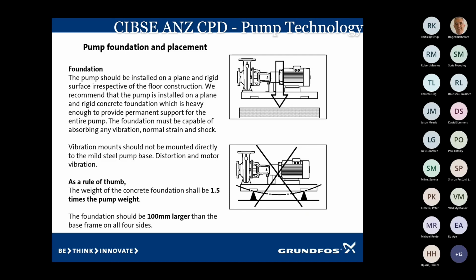If you're going to put vibration spring mounts underneath a pump, never put them under the pump base. These mounts must go underneath the inertia base. When you mount a pump onto the foundation, like the top drawing here, that might be a basement. And if you've got a basement and there's nothing underneath it, there's no reason why you can't put that pump on its steel base and pull it hard down onto the concrete. As long as the mass of that concrete is 1.5 times the mass of the pump and the motor, it'll all work fine. And then the vibration will go into the foundation. It'll be absorbed into the foundation.